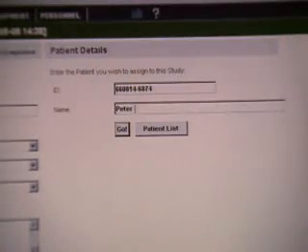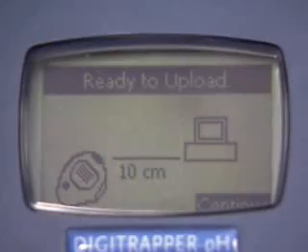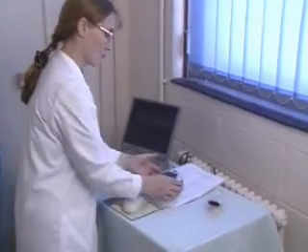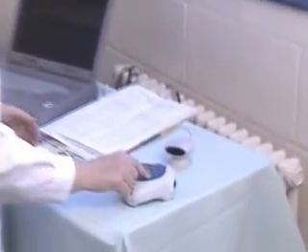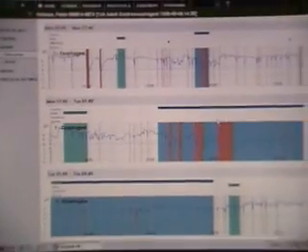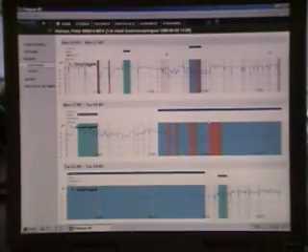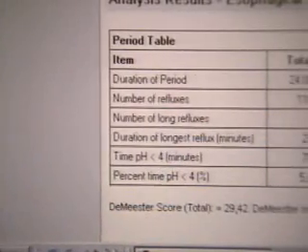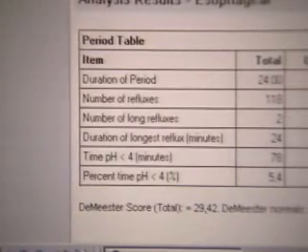The patient's demographic and diary card information is input to the system, and the pH data is captured by the computer system via an infrared detector and the automatic analysis performed. It is important to review the entire procedure to check for any possible loss of signal or artifact. Signal loss can be caused by a loose reference electrode. Next, review the data tables for correlation with the raw tracing.